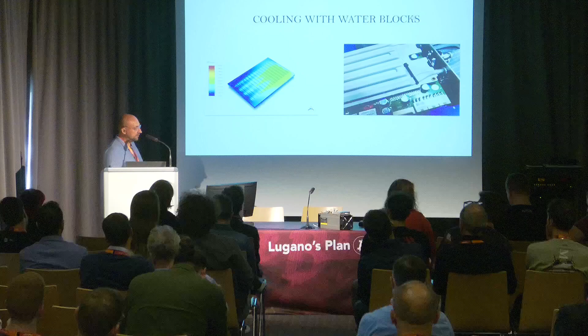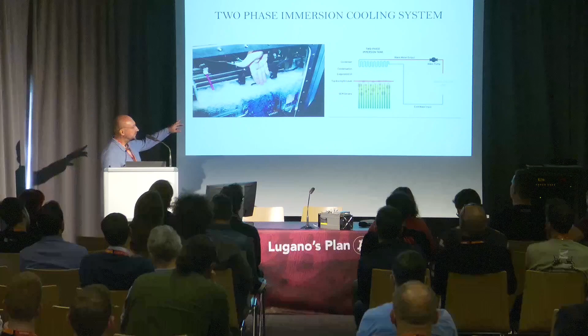The next very popular method of cooling is so-called two-phase cooling. This means the equipment is submerged in a special dielectric liquid. It's dielectric, so it works perfectly below the level of the liquid, and that liquid boils at a lower temperature. Once it boils, it's very efficient because it changes phase from liquid to gas, and that process takes a lot of heat from the chips.